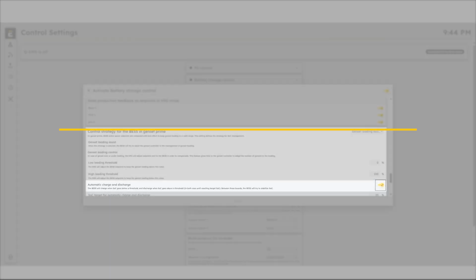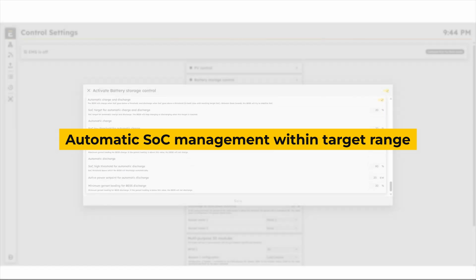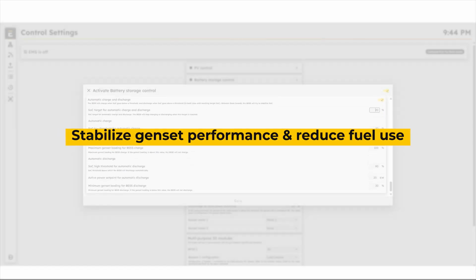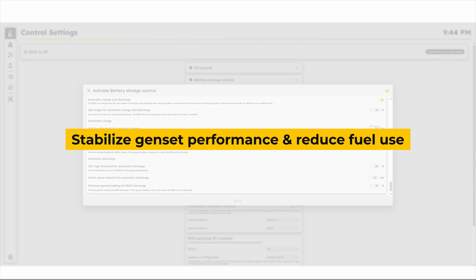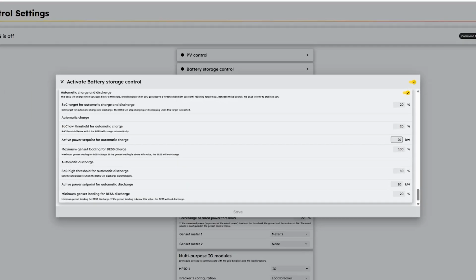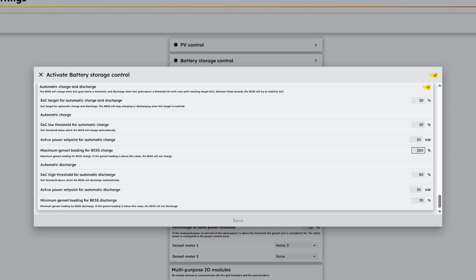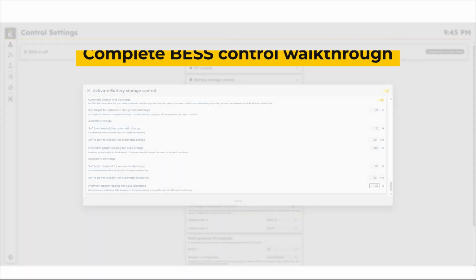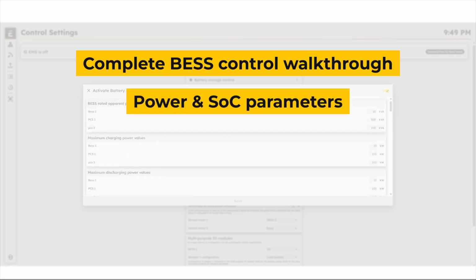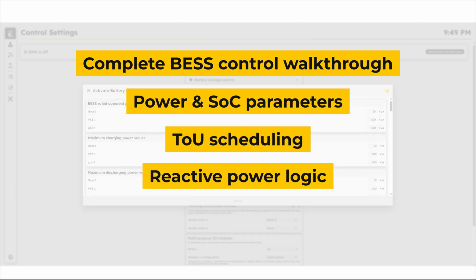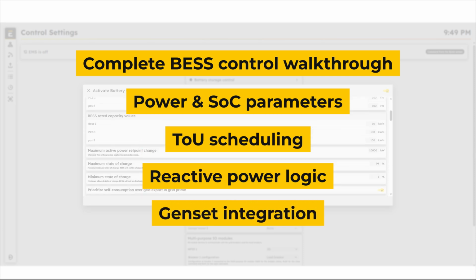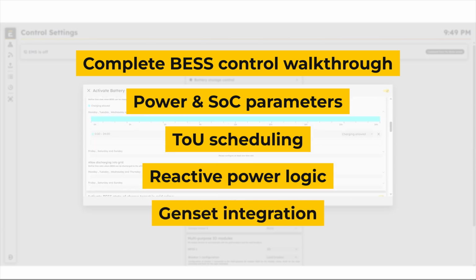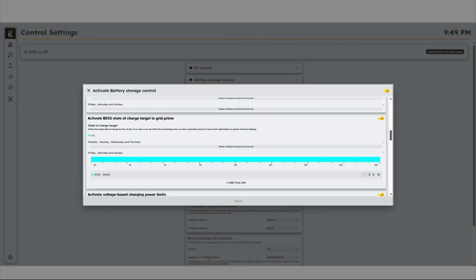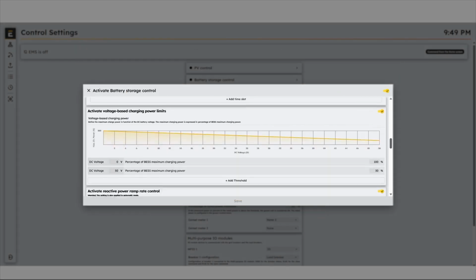With automatic charge and discharge enabled, the EMS automatically manages power adjustments between charging and discharging of the BESS based on SOC and load conditions. This ensures smooth power flow, longer generator life, and stable operation within the defined limit. We've now completed a full walkthrough of BESS control configuration, from defining power and SOC parameters to setting time of use schedules, reactive power logic, and genset integration. These steps ensure reliable performance, efficient energy usage, and safe operation across all hybrid sites.